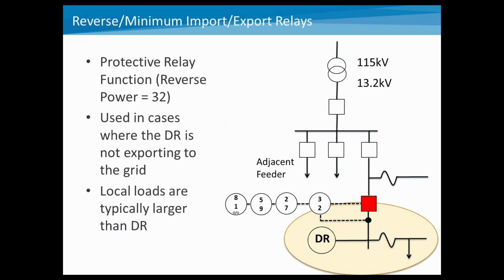So first off, taking a look at things like minimum or reverse import-export relays, what that means is they basically set a relay. If you look in the figure where that red box is the breaker, you may have some relay functionality attached to it. These numbers, 81, 59, 27, and 32, are relay functions. 32 is reverse power, and in this case, if the power is ever reversed onto the utility grid, that would trip that particular breaker. This is for what utilities typically call a non-export type condition. And if you're set to never inject power back onto the grid, this is typically used for that case. Now, a lot of times, this is when you have a large local load.